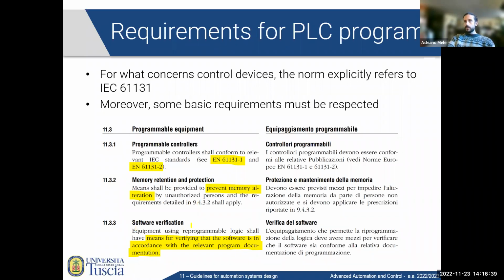Third, we have software verification. Equipment using reprogrammable logic shall have means for verifying that the software is in accordance with the relevant program documentation. Okay, so again, you should be able to verify that the software is working as expected.